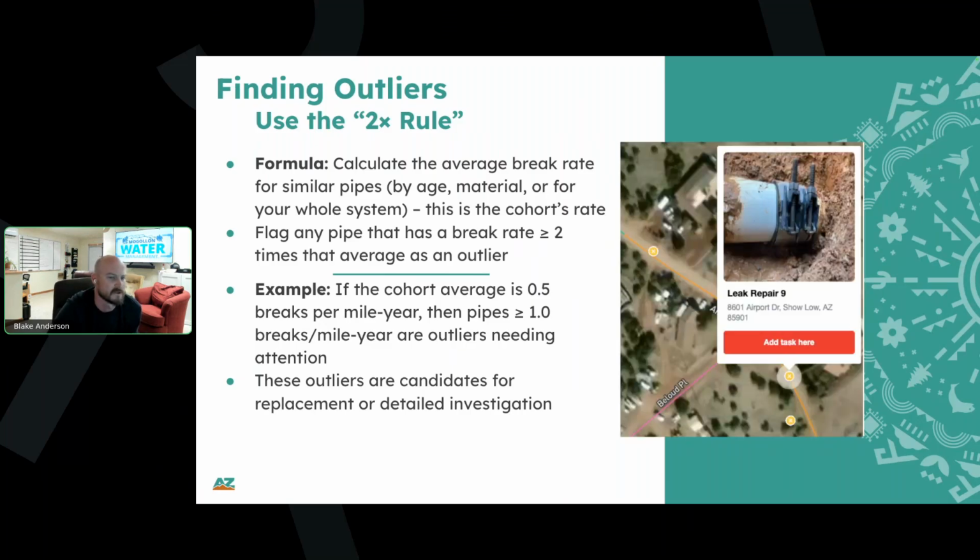If we zoom in, we get a closer look. We find that in the past 2 years, we've made 5 repairs on this section of line. So that's 2.5 per year. Additionally, when we look at the data, we find that every one of those repairs has been on a leaking PVC glue joint. They glued the fittings together because they were cheap. It's the same kind of repair on every single one of them: these joints start leaking, and then we have to put a clamp on the end of it.